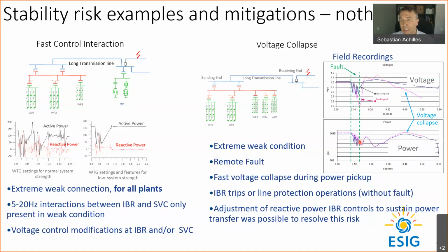Now, after the initial transient, the active power starts increasing. And when the active power starts increasing, the voltage starts collapsing, and this basically ends up collapsing. There was a voltage collapse in this case. The voltage collapse is relatively fast. It was like a 200, 300 millisecond phenomenon, and that's fast. The voltage collapse is as fast as the active power recovery, in this case from the inverter-based resources.